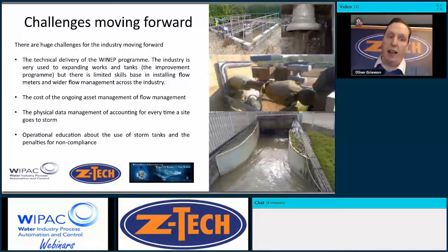Is the site in wet weather conditions when it was going to storm, for example? Was it raining? Both the pictured sites there, the answer was, of course, no. Both were bouncing penstocks. Was it treating flow to full treatment with an uncertainty measurement? All of it needs to be managed, mapped, and understood.